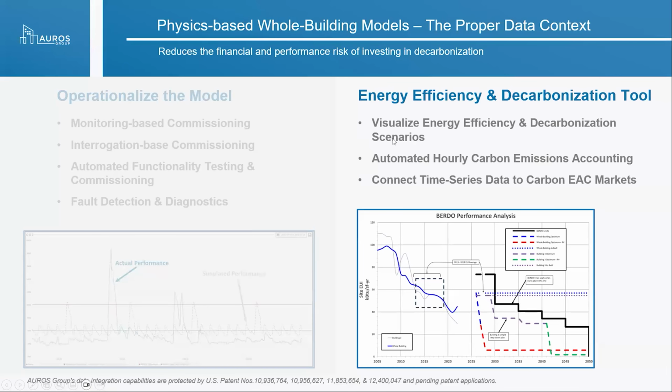So think of a model or building, right? If I go into an existing building and I create my first model, I want to make sure my model is validated, that the work I'm doing with the model is working from a calibration point so that any deltas from that are going to be actual. So the first model we create is called the operational model. We calibrate it back to the building, and we can calibrate our models to under 1% of the building using the ASHRAE 14 guidelines. Then we want to create scenarios.